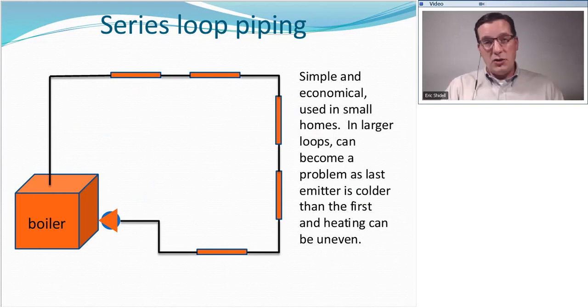Now, what should have happened originally when this system was constructed is, if we're using copper fin baseboard, which most of them do, if this room and this room are the same size room, this baseboard should be bigger than this one to account for that difference in temperature. But most of the time when these were put together, that wasn't done. Or maybe it wasn't possible because both these rooms are the same size and you can't fit more baseboard in this one. Possibly. Or they just bought 6-footers for all the rooms and that's what they put in there. Sometimes you'll see that too. When maybe they should have had a 4-foot in this room and an 8-foot in that one. Just, you know, for example.